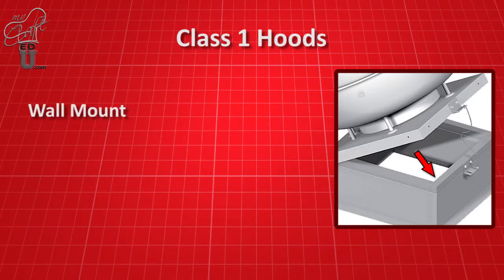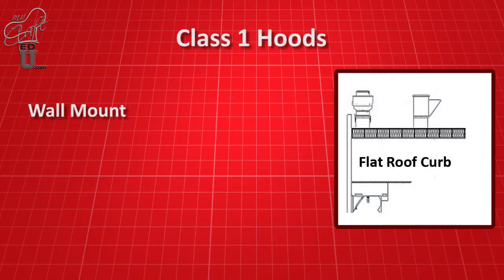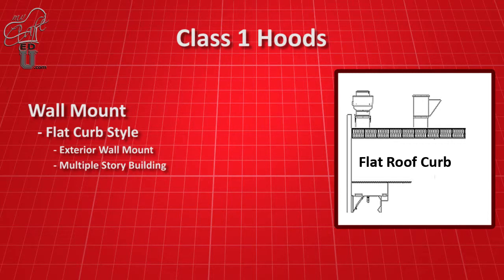Now, fans and curbs can be located in 3 primary locations. The first is the wall mount application. Wall-mounted fans require a flat curb that is mounted on the exterior wall of the building. Wall mount fans and curbs are typically utilized when there are multiple stories or floors above the kitchen area.